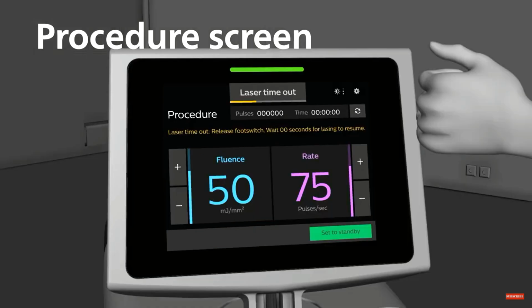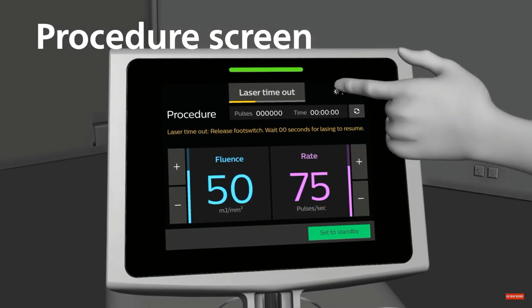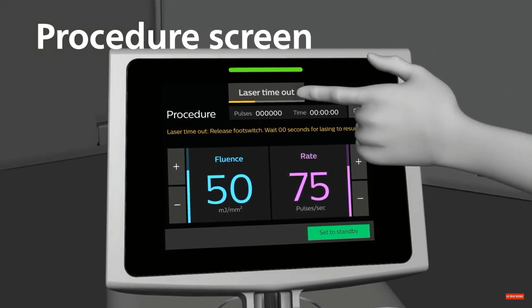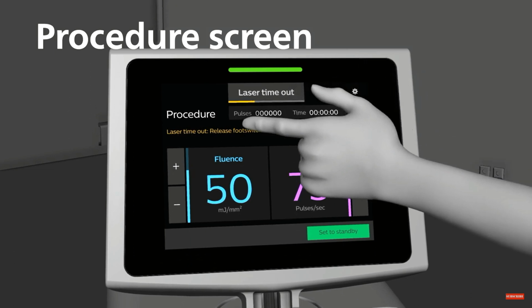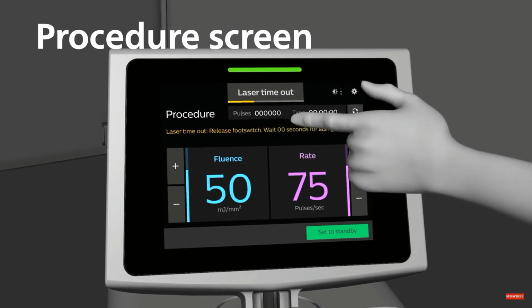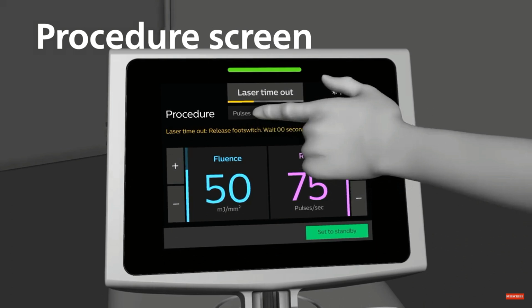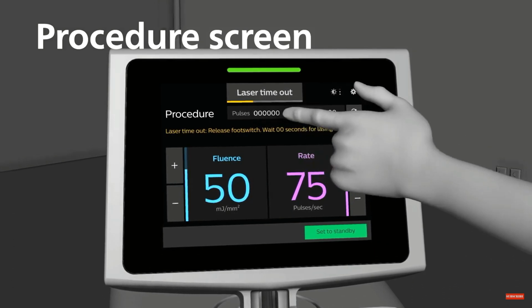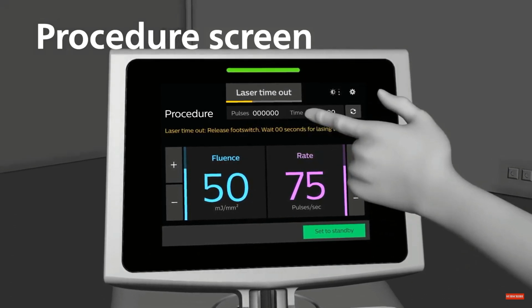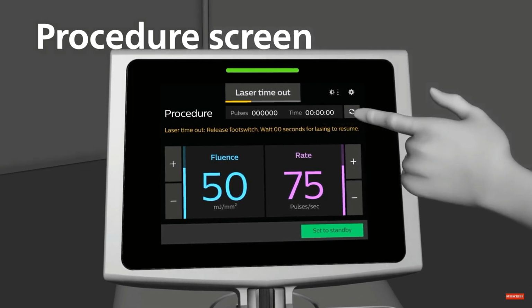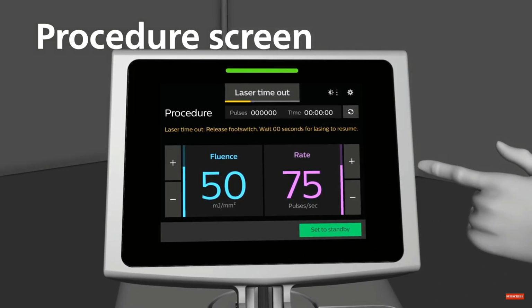If using a coronary or lead removal fiber catheter, there will be timeouts once you activate the laser. The system will provide a visual display of the remaining time left in the timeout. Once the timeout is complete, the system will provide audible feedback to notify the user. On the touchscreen, you have a running total for pulse and time. The pulse display shows the total number of pulses during a procedure. The time display indicates the total lasing time of the procedure. There is also a reset button to reset the pulse and time displays.